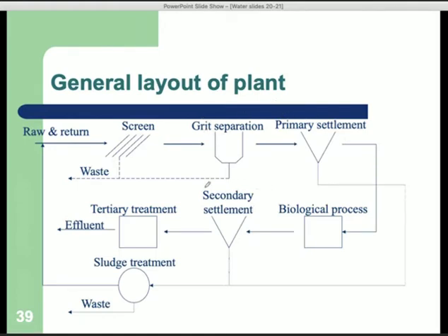So it's similar in a sense to the water treatment plant I mentioned first. You have your raw wastewater going in, goes through screens. These screens will be just metal bars or something, maybe the size of my sausage fingers here. Anything that goes through the metal bars goes into the treatment plant, and anything that doesn't is raked off and goes into a container, landfill, or whatever it may be. That is primarily to keep out dead sheep and whatever flows down the river, but it's also to a degree to protect the machinery, because smaller particles would get into the bearings of things and so on.